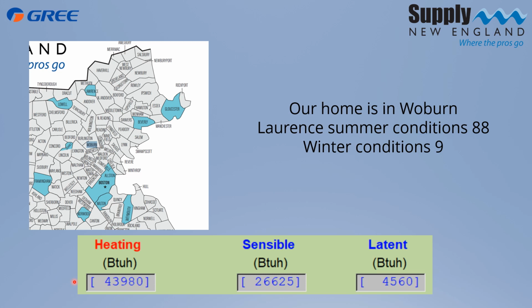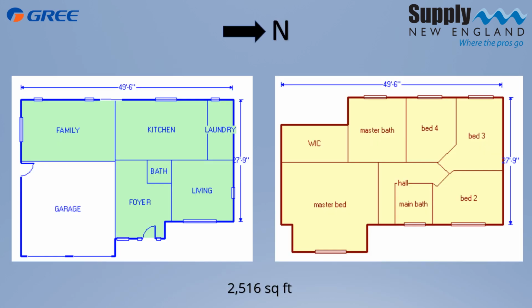Based on 75 degrees indoor and 88 degrees outdoor, for our cooling numbers we have two of them. They're called latent and sensible, and we'll be talking about the difference between those later on. Our sensible needs are 26,625, and our latent needs are 4,560. That's what we're going to be starting with. This is our home. It's about a 2,500 square foot home, two stories, living area on the first floor, four bedrooms on the second floor. So that means that we have five people in this environment.